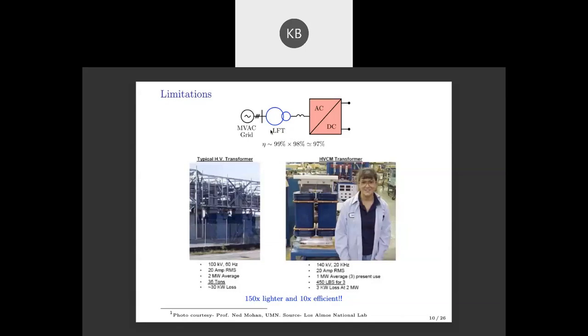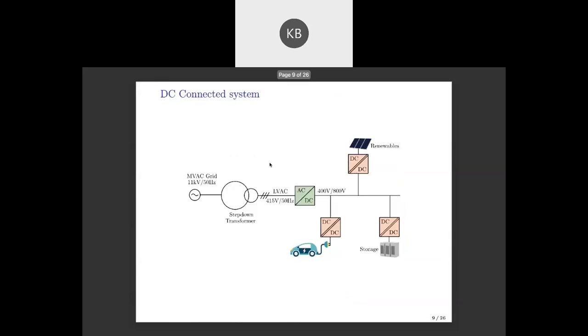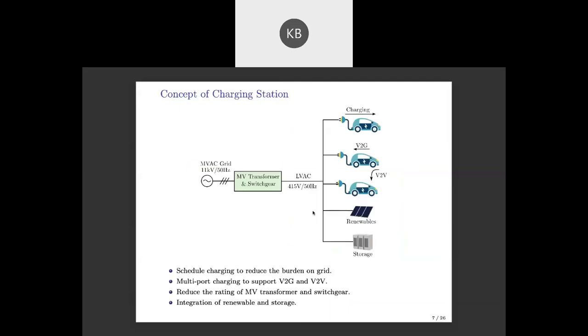If you just take a half megawatt step down transformer, it is going to be very heavy. And in fact, in that AC connected system I just talked about, this medium voltage transformer and the switch gear accounts for, and is probably one of the most expensive and one of the largest components in the entire charging station.